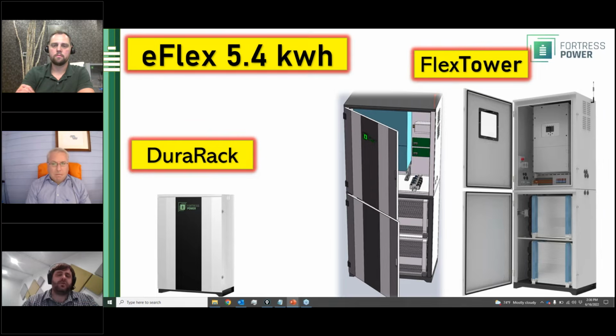The Flex Tower is the DuraRack plus an upper cabinet that can mount up to a 15 kilowatt inverter. I've checked with Victron, and you cannot fit two Victron 10 kW Quattros into this cabinet, but you can fit one. That allows for easier wiring between the eFlexes. It includes battery cables with a power distribution block, and the wire run between the power distribution block and the inverter can just go up into the cabinet. The cabinet comes with internal fans, so heat generated by the inverter is force blown out with dust filters. There's also a rapid shutdown button and conduit entry points for generators and solar, as well as parallel stacking of cabinets so they can go side by side.